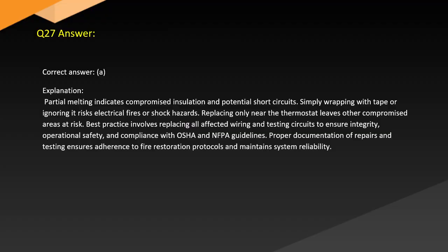Answer. Correct answer: A. Explanation. Partial melting indicates compromised insulation and potential short circuits. Simply wrapping with tape or ignoring it risks electrical fires or shock hazards. Replacing only near the thermostat leaves other compromised areas at risk. Best practice involves replacing all affected wiring and testing circuits to ensure integrity, operational safety, and compliance with OSHA and NFPA guidelines. Proper documentation of repairs and testing ensures adherence to fire restoration protocols and maintains system reliability.